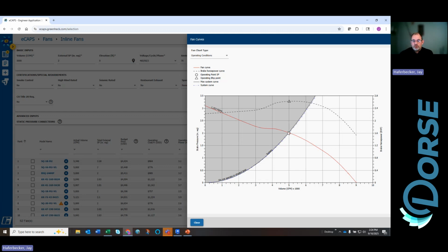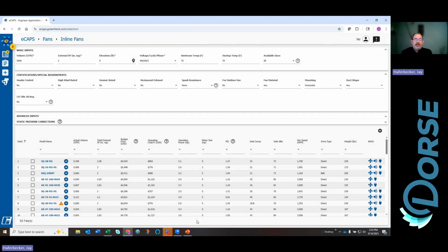But rather than just throwing a line on there, what we did is we put a tolerance on there of about 12%. That brings you out to about where my cursor is. If you're operating anywhere from that line, the gray region, down to about where my cursor is, we're going to caution you on that selection. You can still have it if you want it, but just at least be aware that, hey, this thing's getting close to being unstable, right? So since we get 10,000 selections, we hid that one by default. That is one potential trigger of 7 for a caution icon, right?